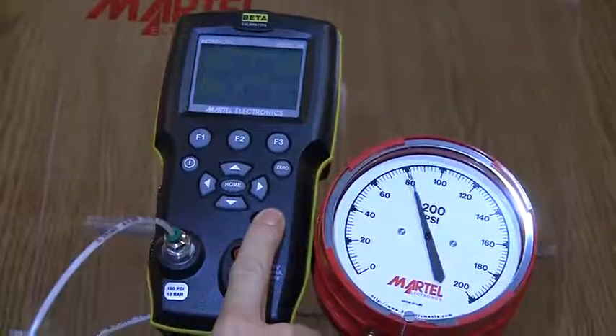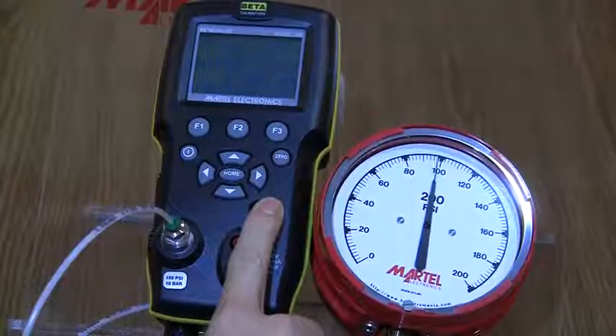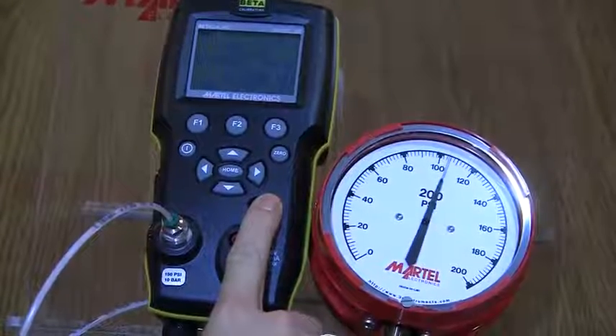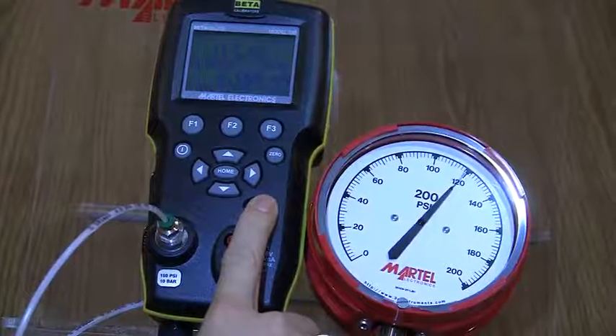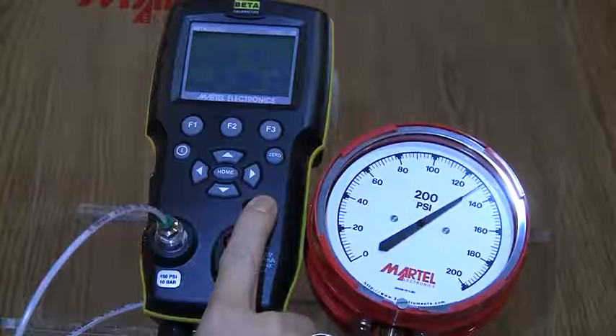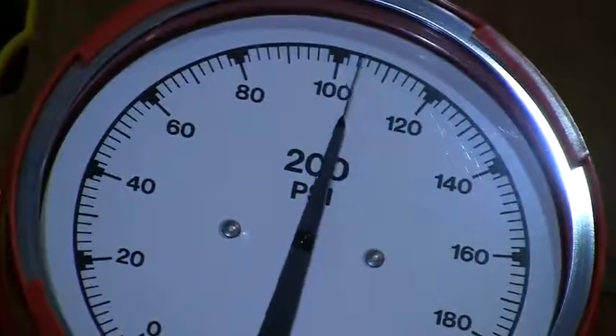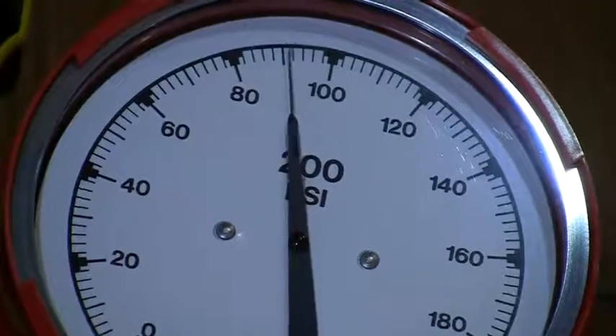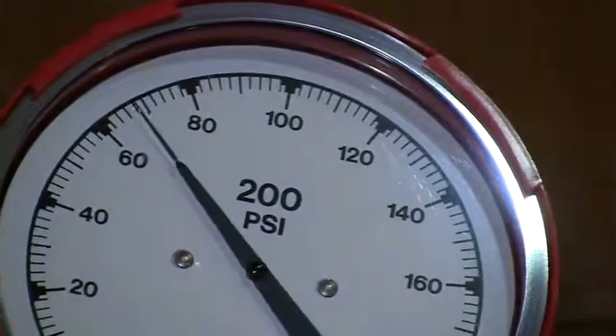The Beta Gauge 330 pressure calibrator is a revolutionary device that can generate test pressures up to 150 psig using its built-in battery-operated electric pump. Most of the time it works perfectly, making it easy and trouble-free to test or calibrate a wide variety of process pressure instrumentation. Occasionally you might find it doesn't generate pressure or doesn't hold pressure — in almost all cases this is due to some contamination of the valves in the pump system.